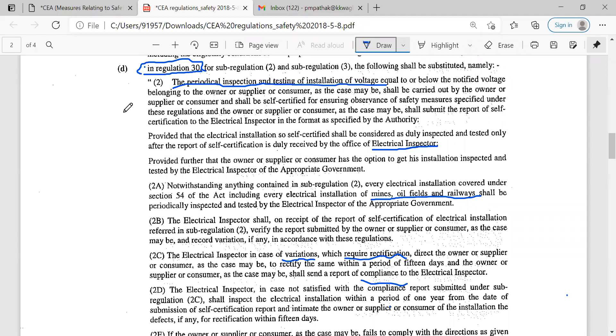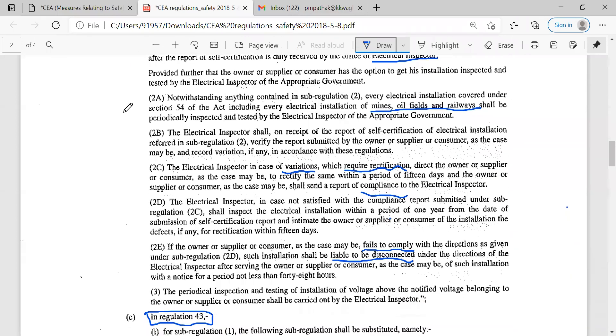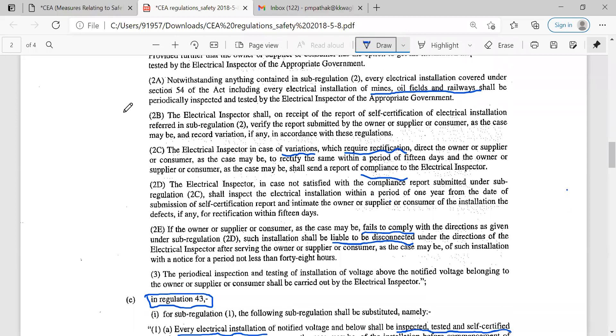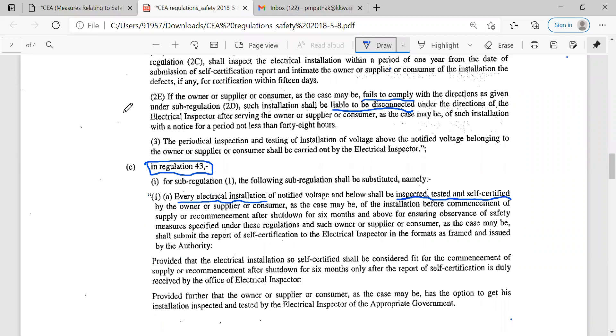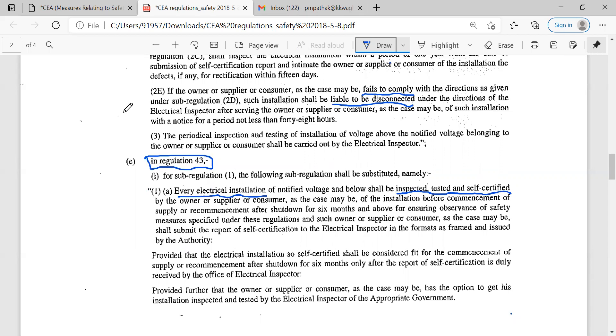Related to mines, oil fields, and now railways also — for these specific fields there are specific guidelines and the responsibility is given to the electrical inspector for the appropriate government. There may be some variations which require rectifications as per the electrical inspector's advice or observations, and that should be complied with. That compliance, those rectifications, all these things should be observed by that electrical inspector and appropriate action should be taken. If it fails to comply, there is liability of disconnection of that electrical supply, and that is the authority of that electrical inspector. These are the changes under rule number 30.